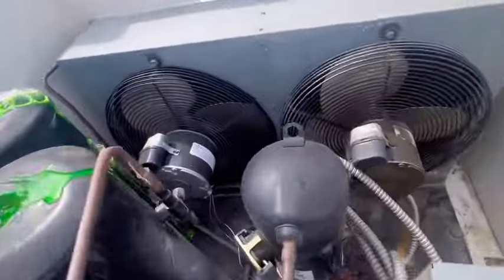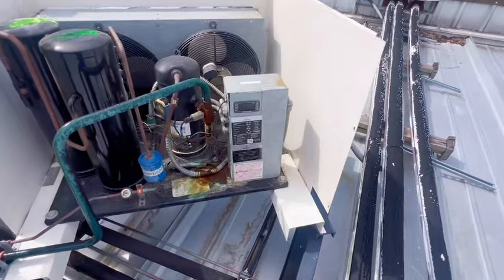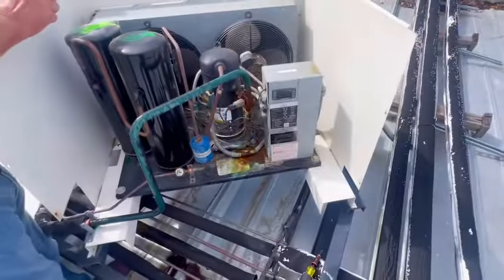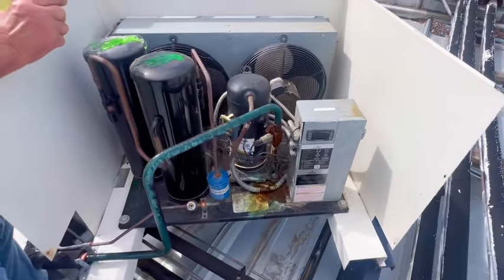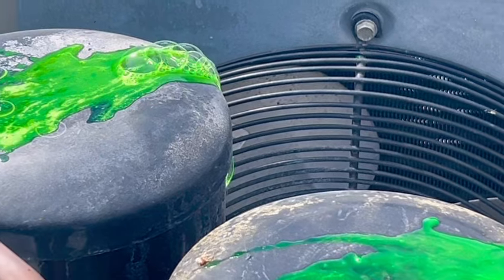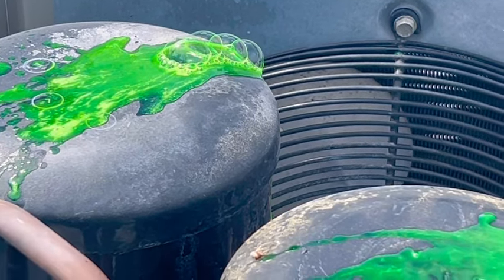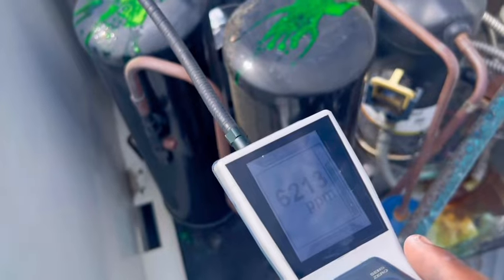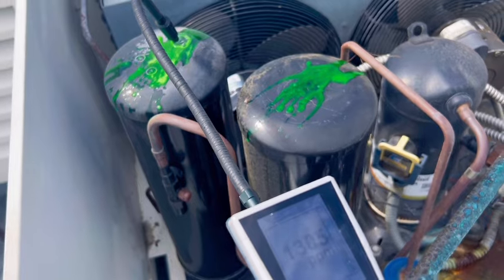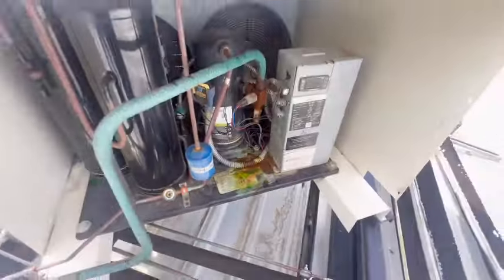If you don't remember, I did replace a condenser fan motor on here before — I have a video from about a month or two ago when the technician found the motor out. Now this unit has another issue where this receiver tank is leaking. These receiver tanks are known to leak — I see so many of them leak. I feel like the build quality just isn't there.